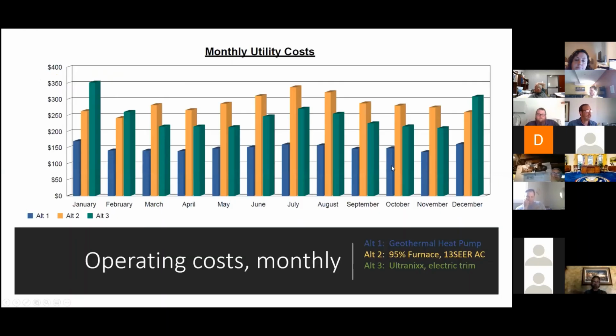Now, looking back at this, if you're doing a retrofit or considering a retrofit, you can just lop that off, and when I say that, I'm talking about the extra cost of electricity in the heating months, because you'll have a gas furnace. So the heat pump stat will be able to enable the gas and you won't need trim heat. So the heat pump will operate as efficiently as it can. When it falls below set point, the gas will be engaged and you'll be using 60 cents a therm to operate. So if we had 420, 520, 570, maybe we get to about $600 a year on 3 tons.